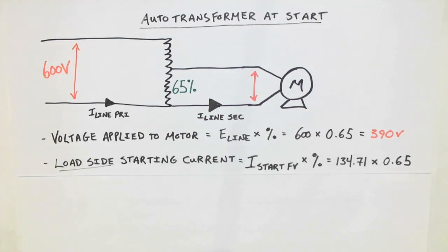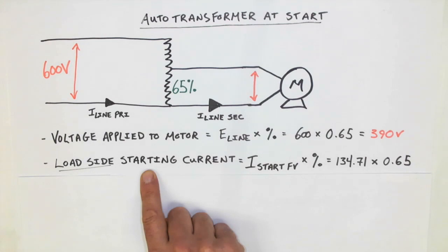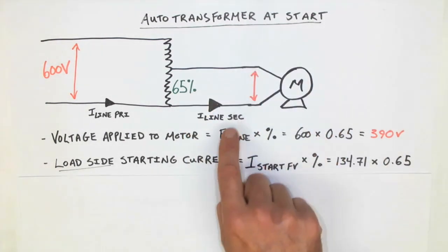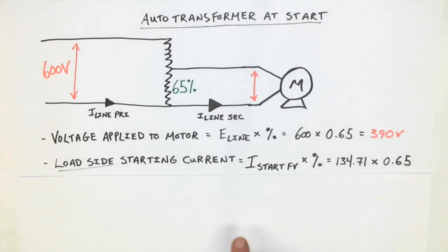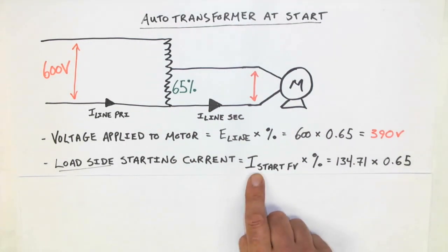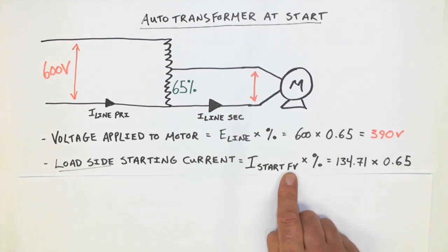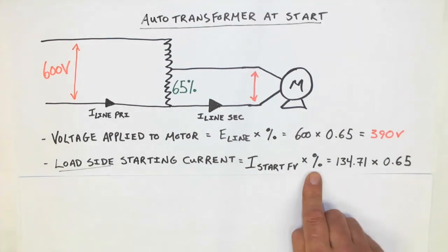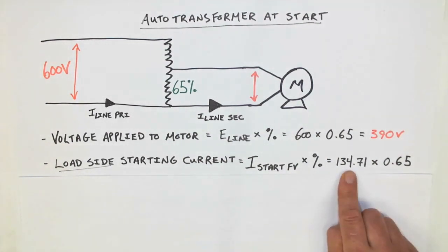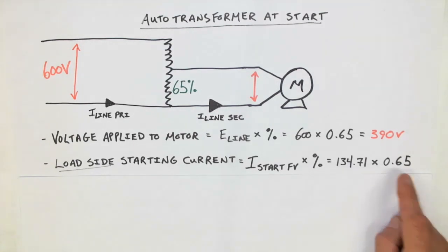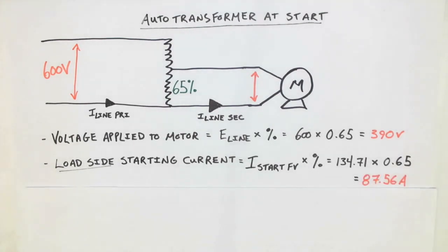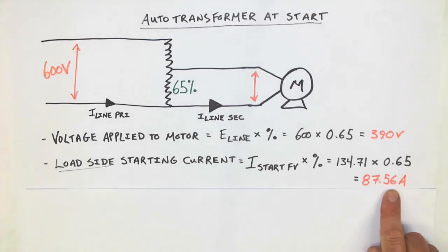The load side starting current. Well, the load side starting current is over here. We could call it the secondary current. The load side current is going to be found by taking the starting current at full voltage multiplied by the percent that was given. So 134.71 amps times 0.65. This gives us a load side current of 87.56. That would be right here.